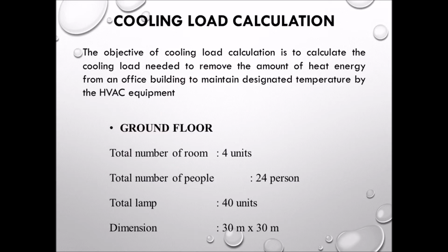The objective of cooling load calculation is to calculate the cooling load needed to remove the amount of heat energy from an office building to maintain the designated temperature by the HVAC equipment. For the ground floor, the total number of rooms is 4 units, total number of people is 24, total lamp 40 units, and the dimension for this floor is 30 times 30 meters.